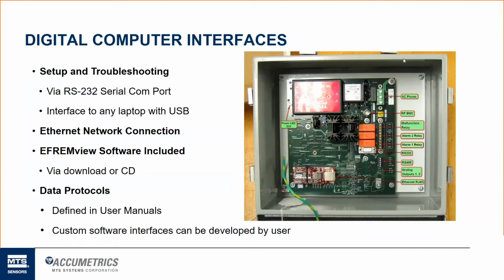Up in the top right is the AC or DC power input into our electronics. As long as that power is brought into our receiver, the telemetry system is going to be functioning. These orange blocks here are the Form C contact relays, and that's why the first one, the malfunction alarm, is a normally closed contact. If there is a loss of power or any interruption, it'll open that normally closed contact, allowing the user to know there's an issue with the telemetry system. The next two orange blocks are alarm 2 and alarm 1, the warning and ground fault alarm. And then there are some other terminal block interfaces for the analog 4 to 20 current loop outputs.